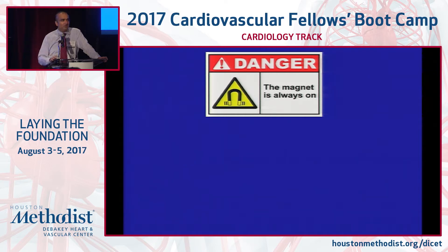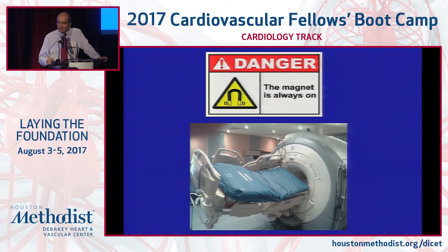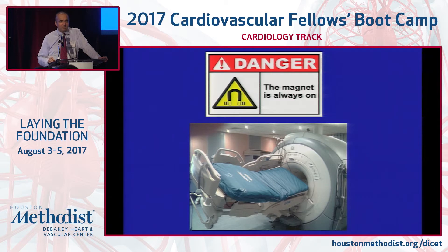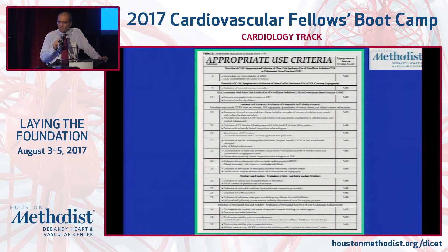You do not walk into the MRI room, even if the patient is coding — you don't go into the room to save the patient. You have to bring the patient out of the room. If somebody isn't careful and takes metallic objects into the room, this strong magnetic field actually pulls the object, and as it gets closer, the strength of the magnetic field gets stronger and stronger to the point where it becomes a projectile. There have been reported deaths where somebody wanted to take an oxygen tank into the room to help a patient having shortness of breath. When you go back to your institution, you can look at the ACC appropriate use criteria — now about 10 years old — which give you an idea of appropriate indications for cardiac MRI.